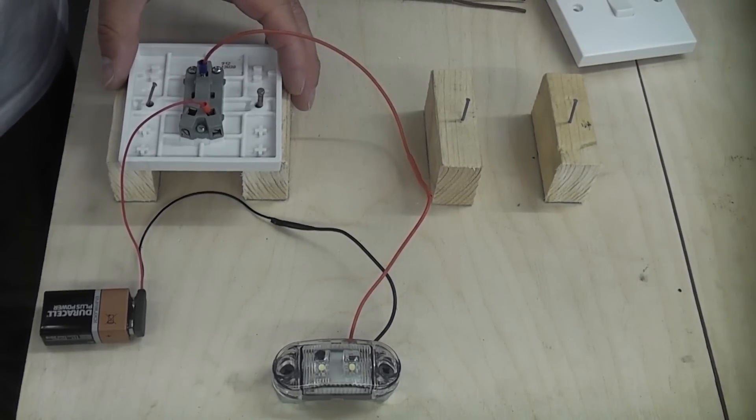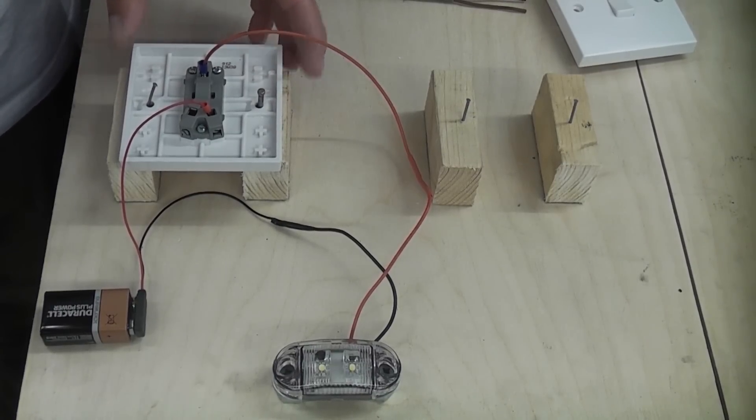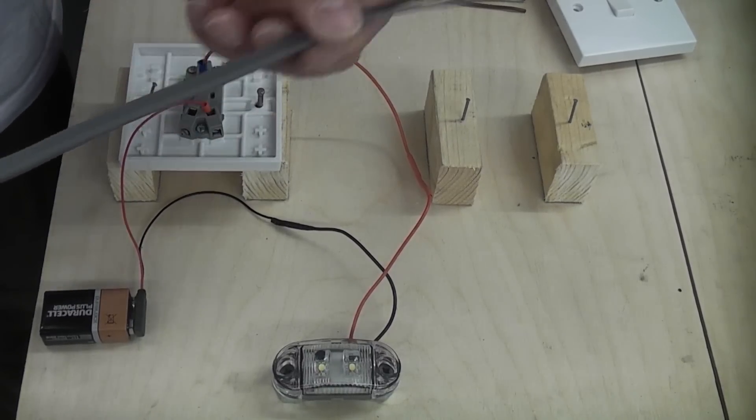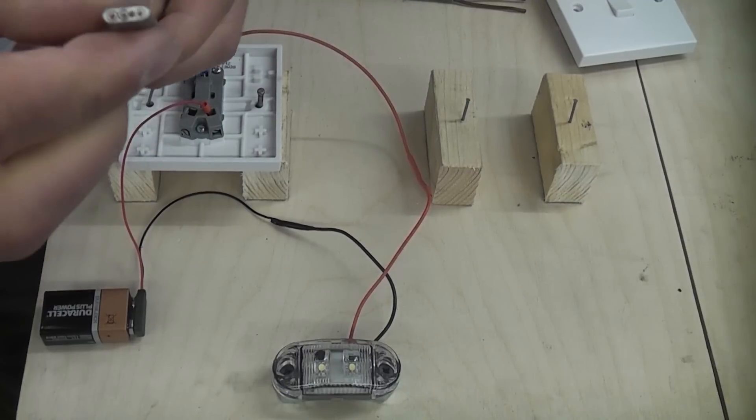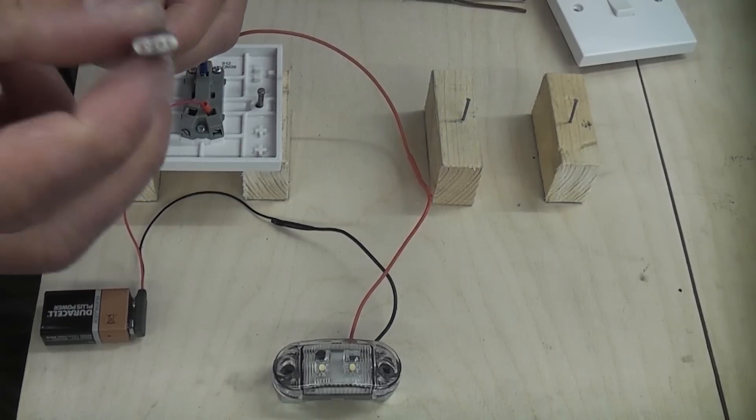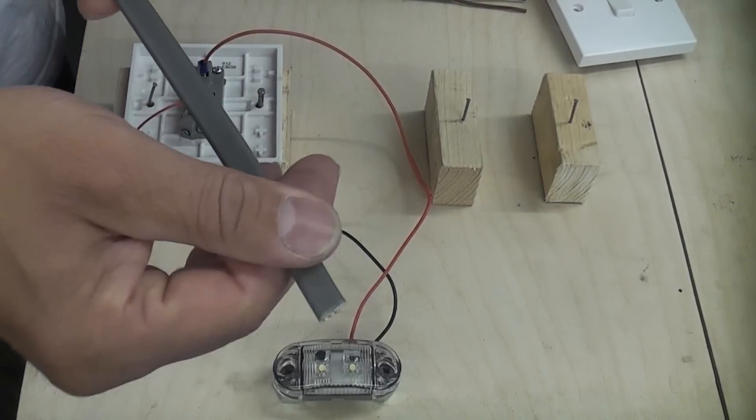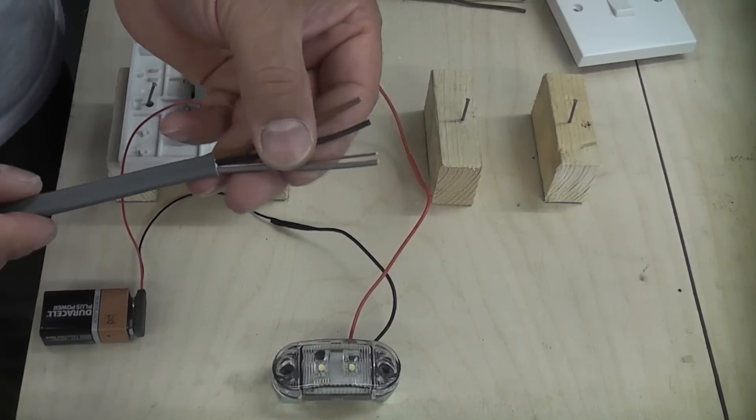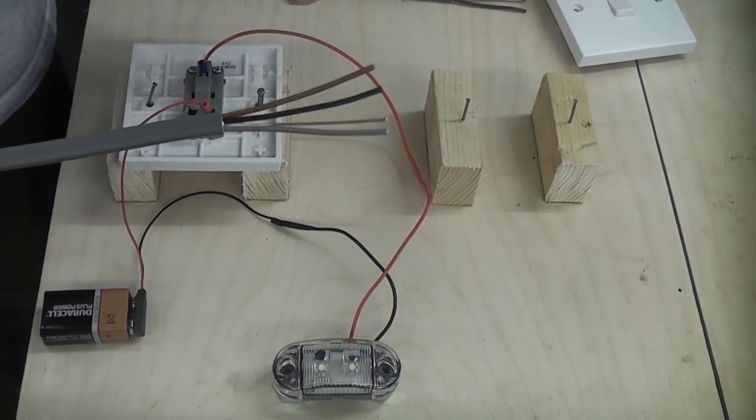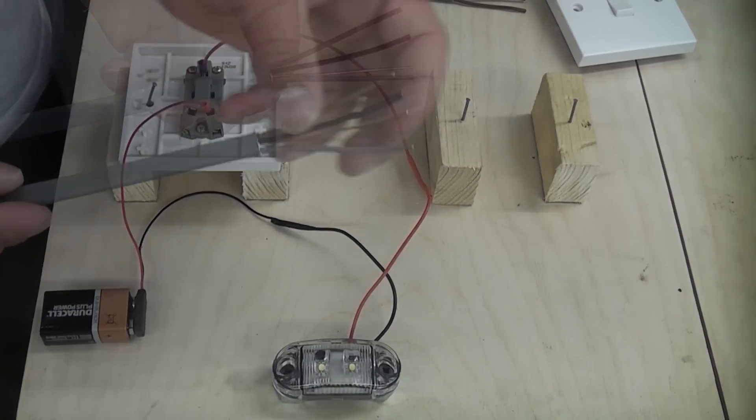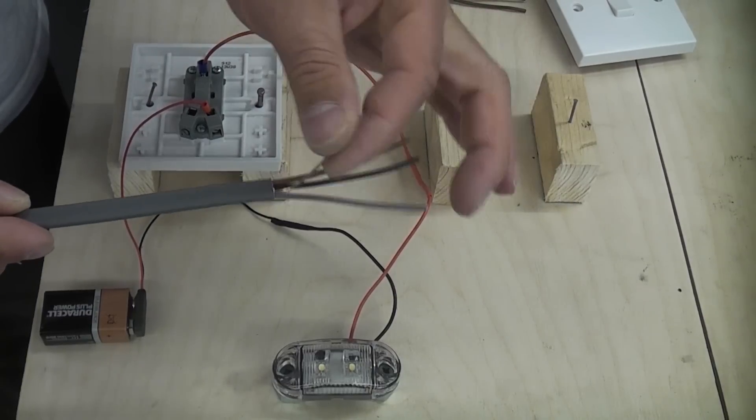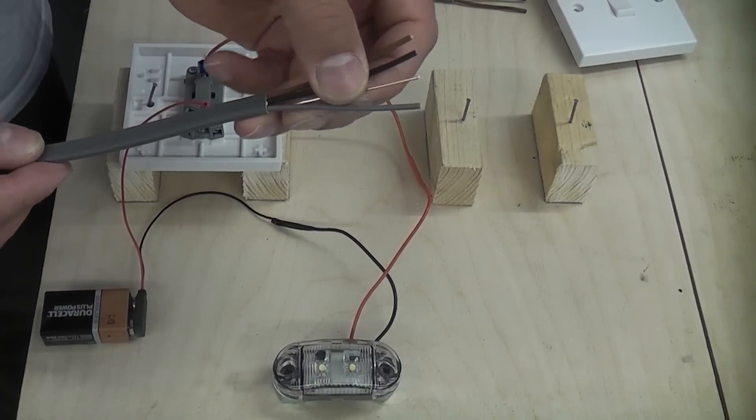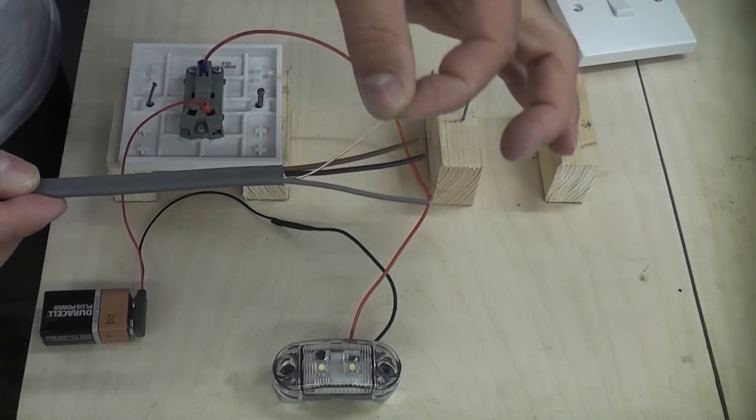This is exactly the same as what you would have at home if you had a lighting circuit in a room, but the cable used to wire it would be a lot different. You would use something like that. So inside there you have the conductors which are insulated and then they are insulated again by this grey sleeving. This piece is actually a piece of three core and earth. This is actually used for doing a two-way or a three-way lighting system. You will notice that this cable has a bare earth wire. That would always be sleeved with green and yellow sleeving in the UK, but for the purpose of this demonstration I'm going to omit the earth wire.